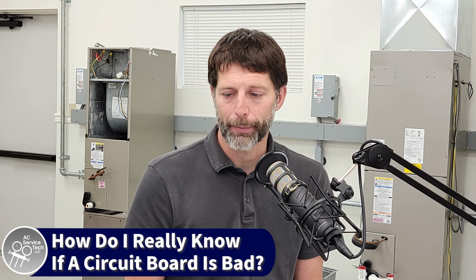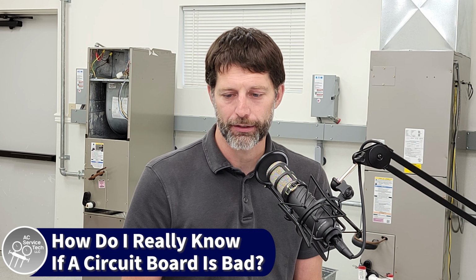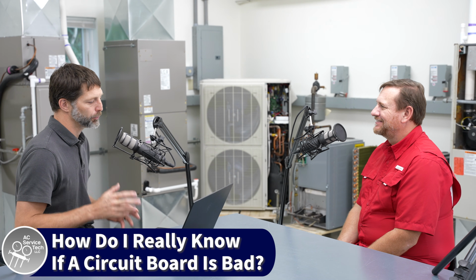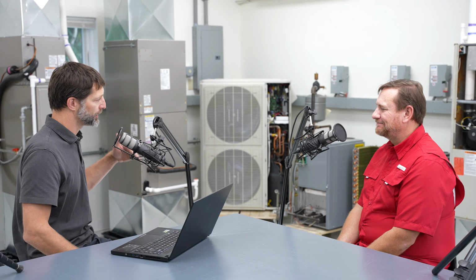Technician by the name of Willie asks, how do I really know if a circuit board is bad? The manufacturers don't give guidance on testing these. With a circuit board, you have a series of inputs and you have a series of outputs. You might have little black boxes on the circuit boards. Those are relays. And so you want to see where each of the wires connect onto the circuit board. If you're doing diagnosis with a circuit board, you don't really want to be doing that if you're drawing current already. So you don't want to be doing that while the blower motor is running. You want to disconnect the blower motor, and you can actually disconnect the high voltage loads in order to check electrical resistance across those little relays.